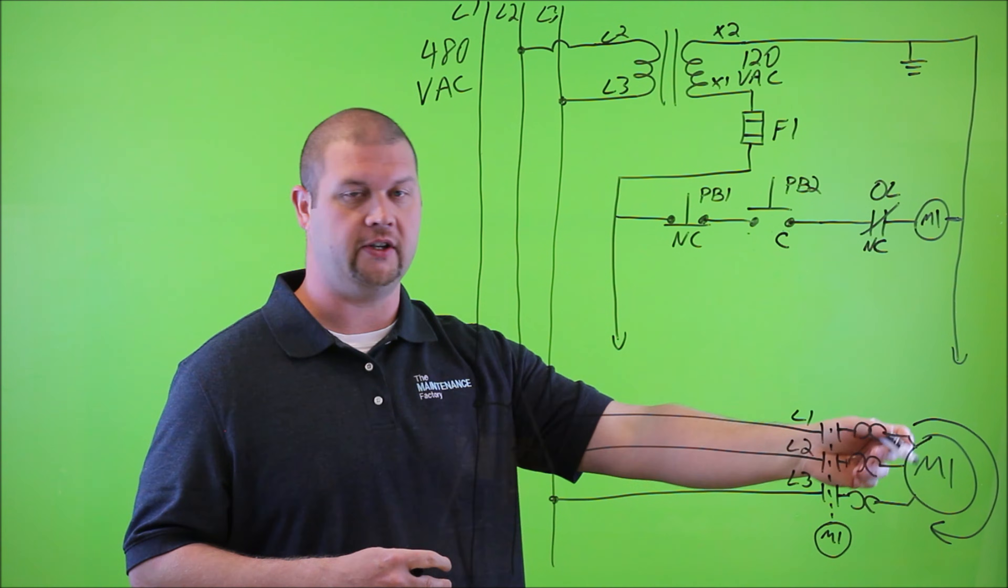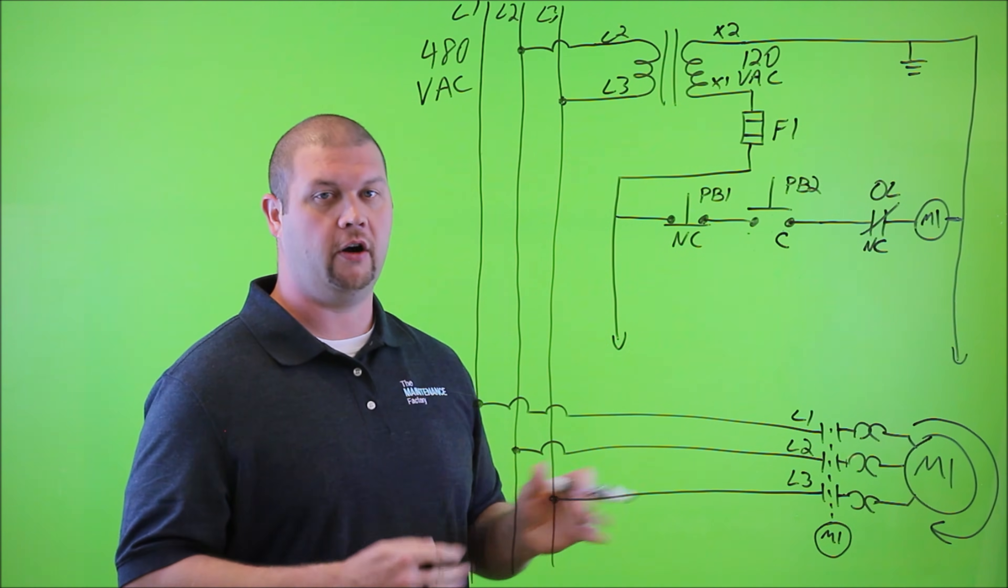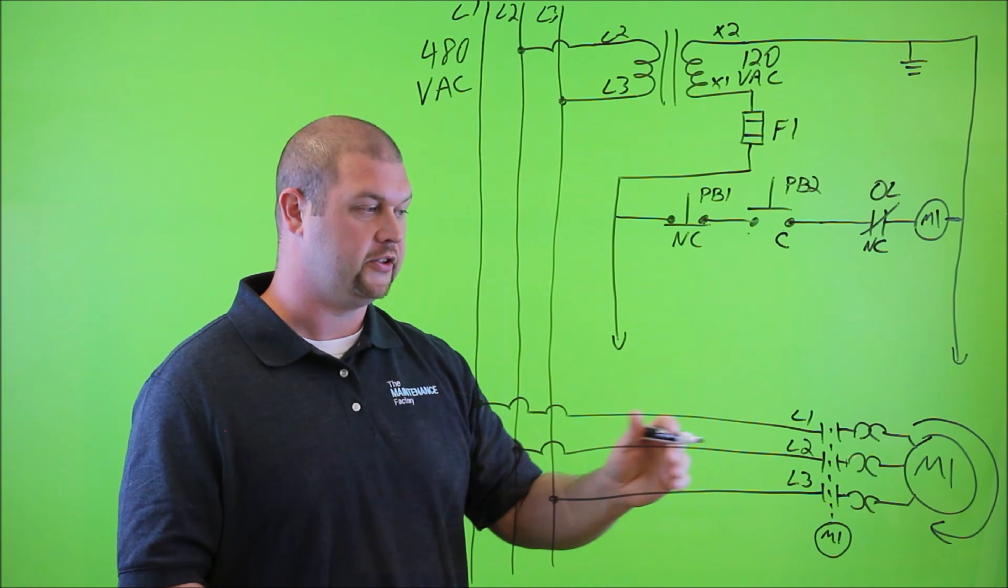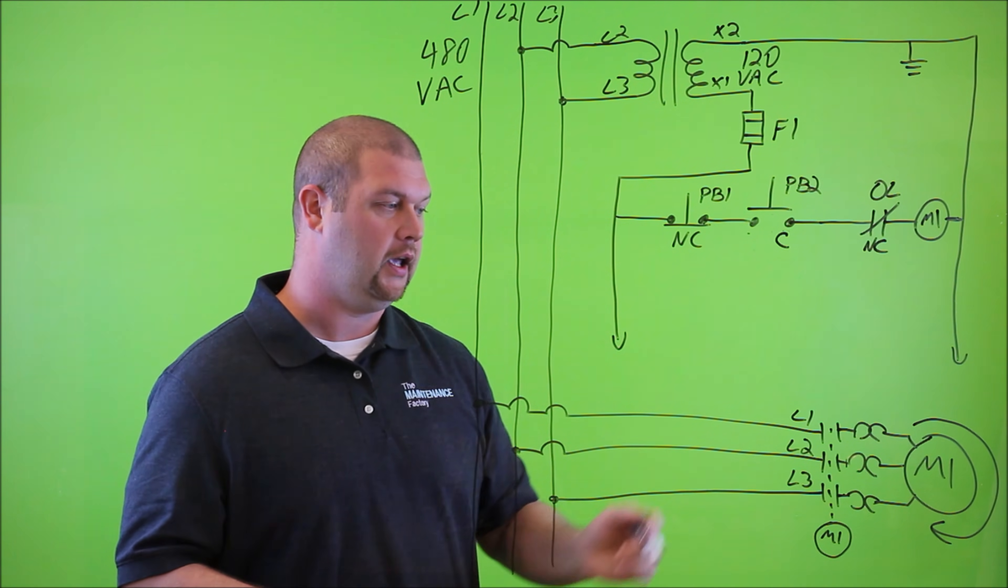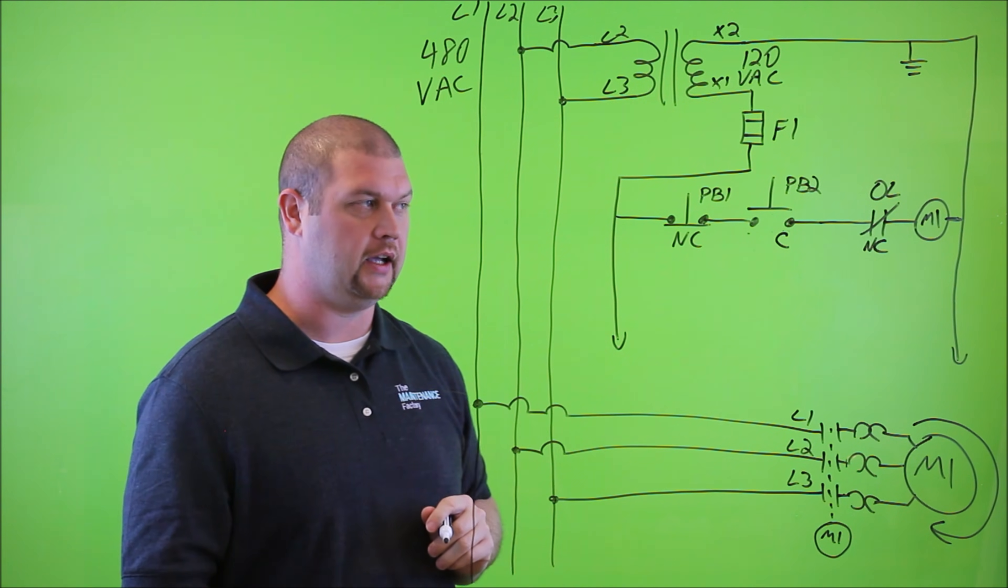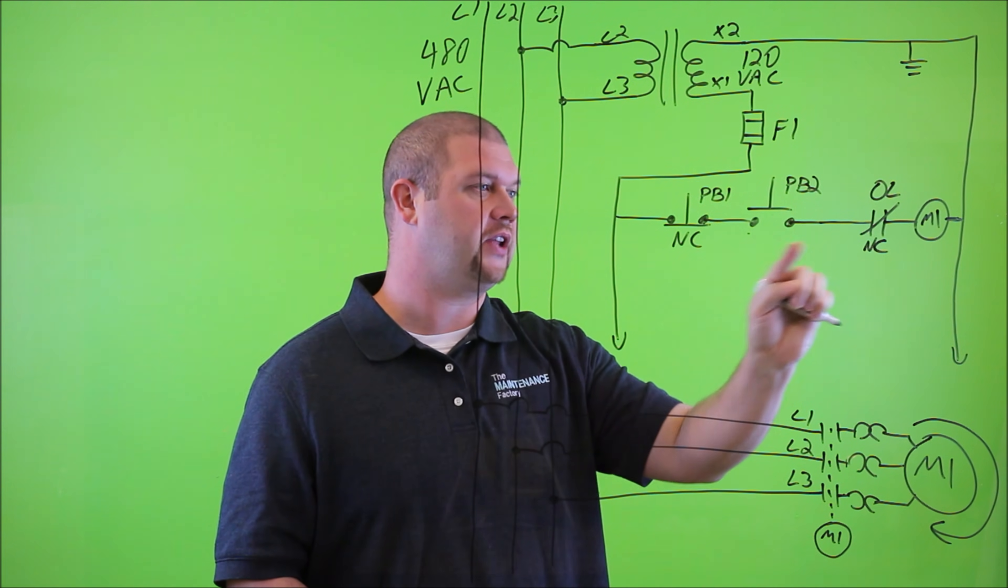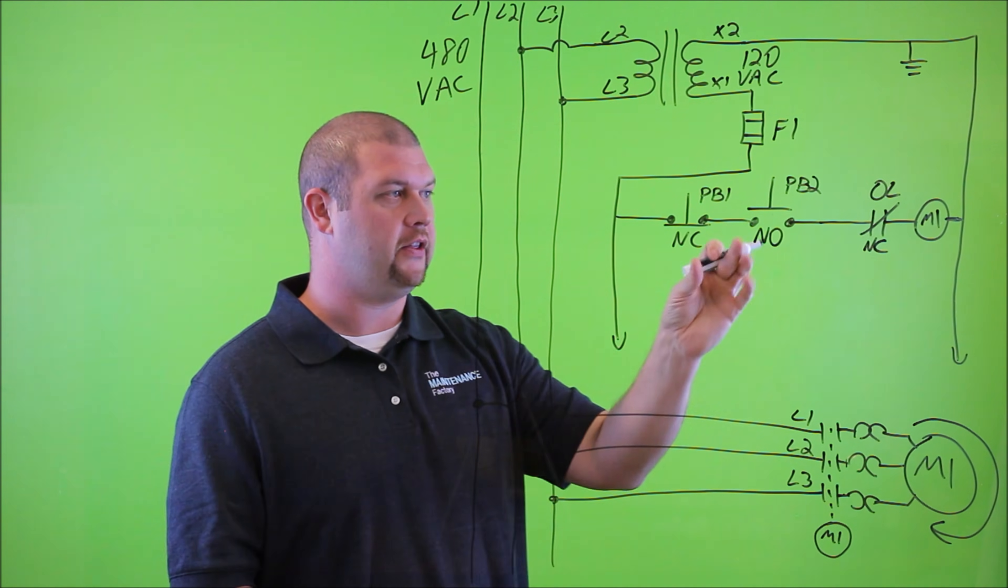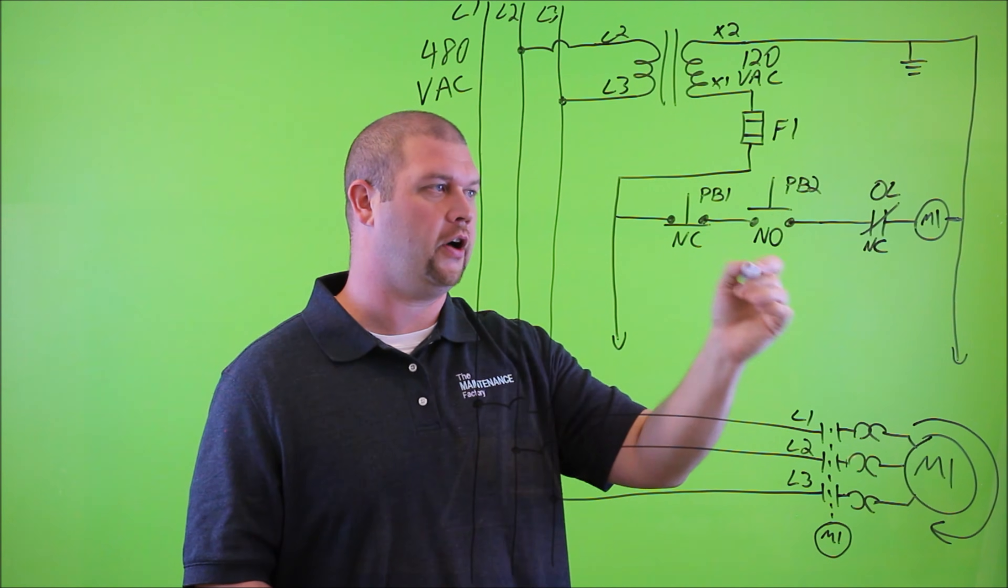Let's say, for example, this is an exhaust fan motor or an intake fan motor, and we don't want to sit here and hold our finger on the start button all day long. So the vital piece that is missing is the memory circuit or the holding circuit, and what we're going to do is draw it in next. Now, where that would need to go, this holding circuit or this memory circuit needs to go in across this start button.